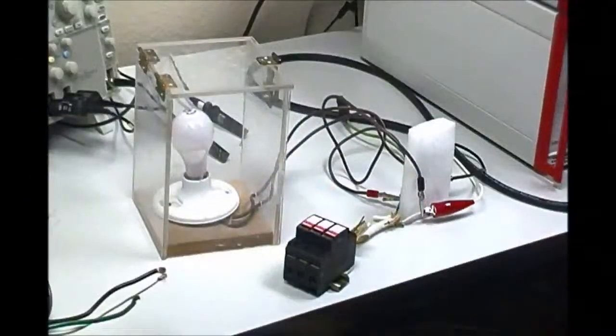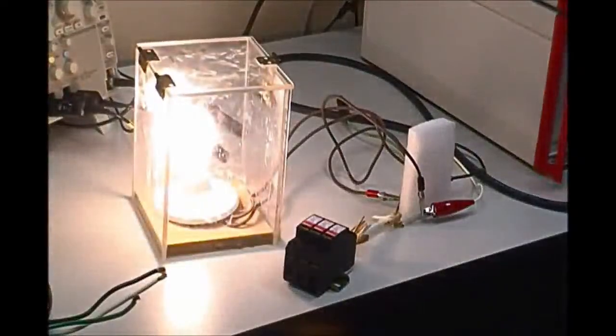Today we're going to run a little 6,000 volt, 3,000 amp surge test on this light bulb circuit and a very popular internationally known surge suppressor, Phoenix Contact, to see what positive benefit it'll have on protecting electrical equipment, but also the electronic equipment that is downstream.